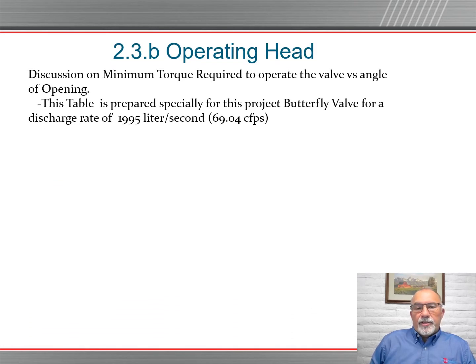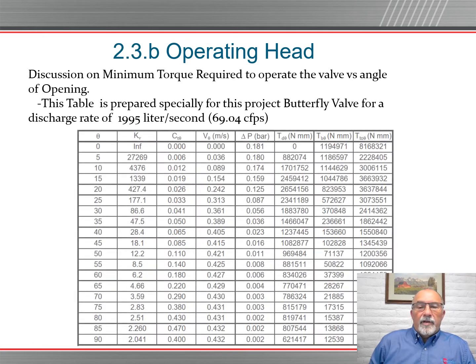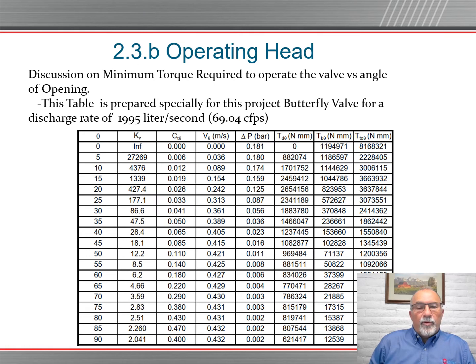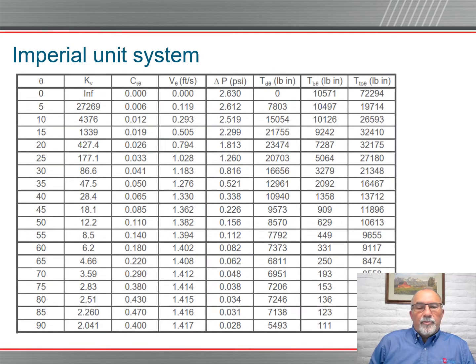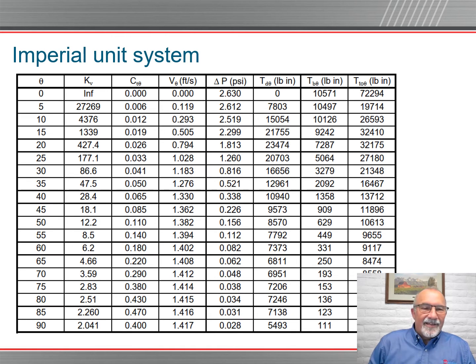The operating head, discussion of minimum torque required to operate the valve versus the angle. This table is prepared especially for this project. The butterfly valve for a discharge rate, again, of the 69 cubic feet per second, or the 1,995 liters per second. There's the table that we use. Imperial unit system, you guys understand probably better than I in Canada what the conversion rates are. So there's a conversion in the imperial unit system that you're familiar with.